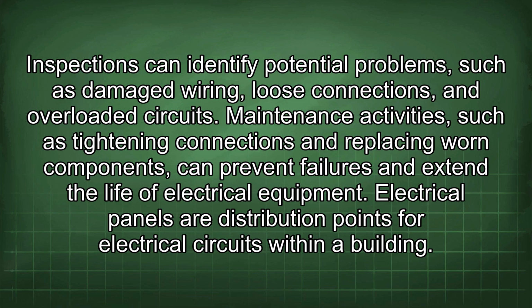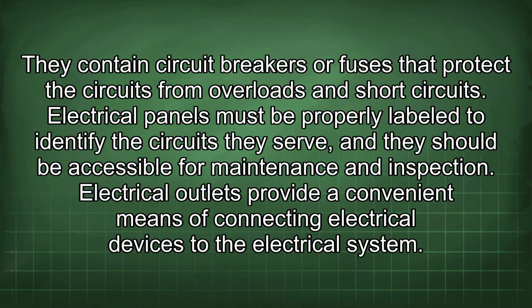Maintenance activities, such as tightening connections and replacing worn components, can prevent failures and extend the life of electrical equipment. Electrical panels are distribution points for electrical circuits within a building. They contain circuit breakers or fuses that protect the circuits from overloads and short circuits.